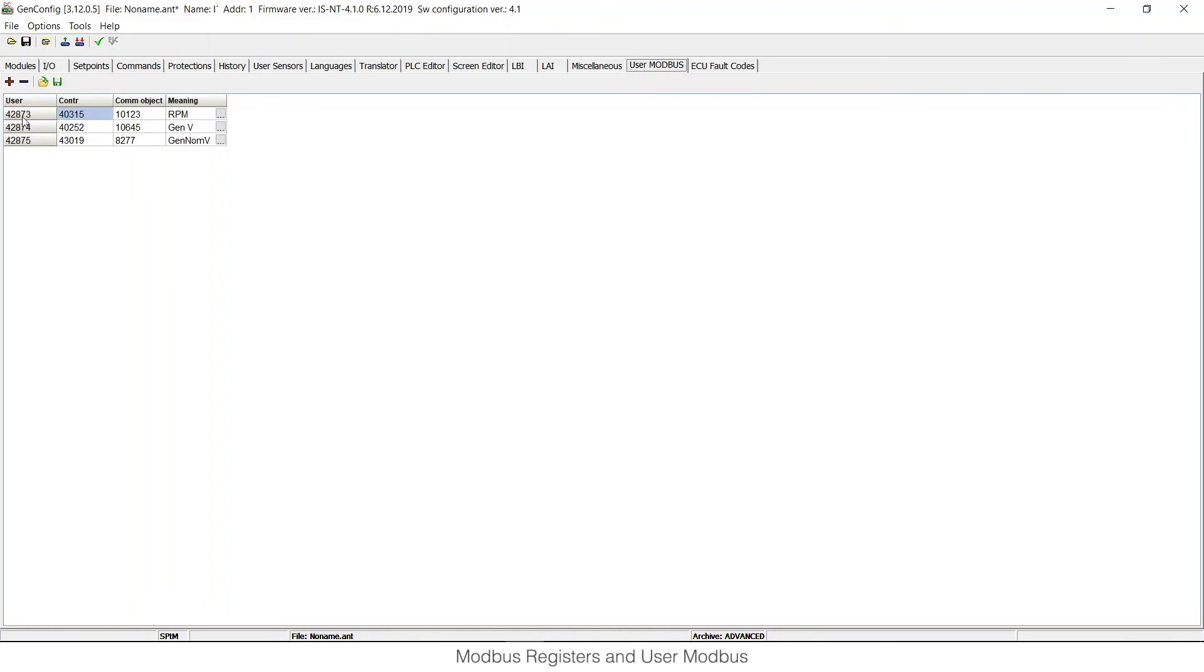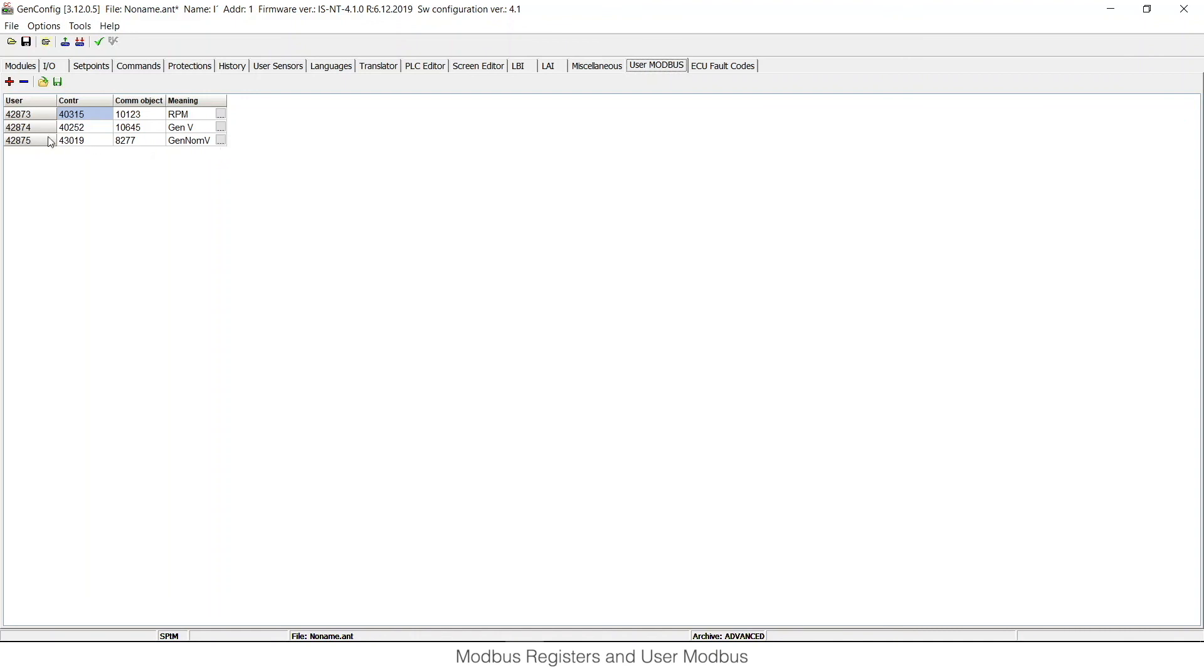Please note that it's not possible to read or write both standard registers and User Modbus registers in one request. So if you would like to read, for example, Gen Set nominal voltage, you need to choose if you would like to read over the User Modbus or through Standard Modbus register. So that's one thing that you should be aware of.